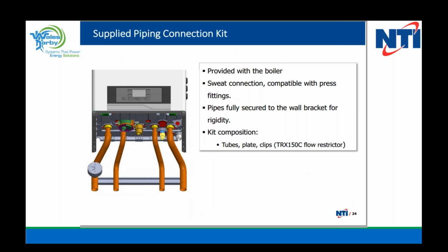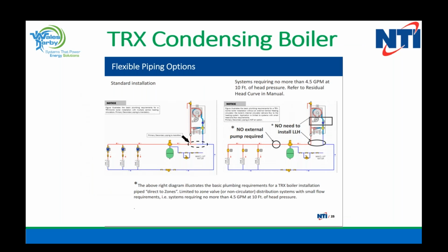All right, so here's our connection kit again. This comes with the boiler. The pipes are fully secured to the wall bracket for rigidity, and the kit composition, like we said, is tubes, plate, clips, and flow restrictor. So, piping options here. Here's to show you what we're talking about because of this heat exchanger. If we've got a flow rate that's 4.5 GPM or less, and the pressure drop through the whole system is not more than 10 feet or less, we do not need to pipe this in a primary secondary fashion.